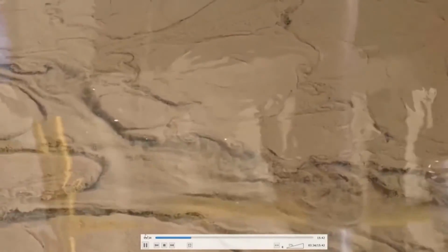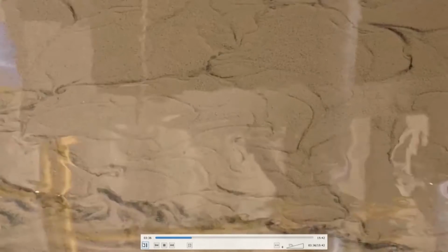So this is when we stop the aeration, right after they stopped aeration, and you see these flocks. Okay, this is a good angle. You can see the flocks, right? All these are flocks, and you can see already, let's say, 1 centimeter of clear water above. So these flocks are settling down by gravity now, right? So it takes some time, again 1 hour, 1.5 hours, or 45 minutes, depending on the cycle that they have optimized.